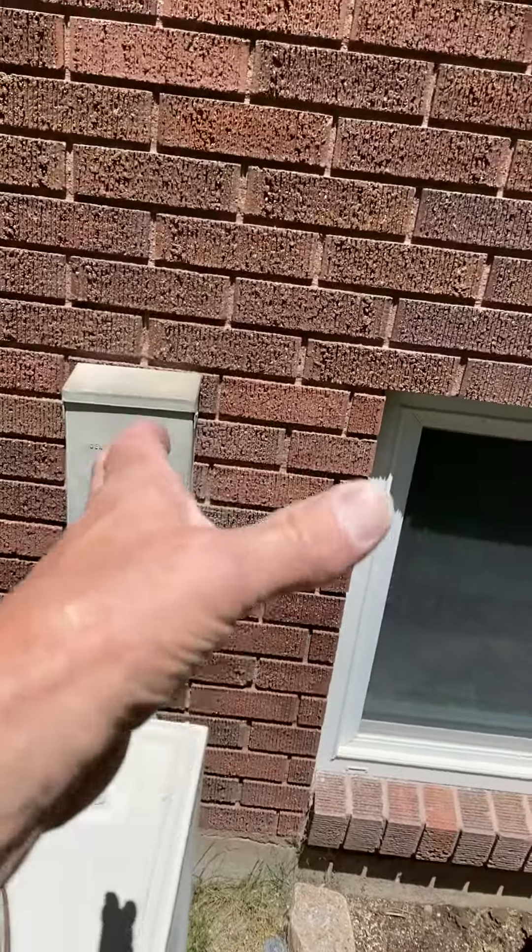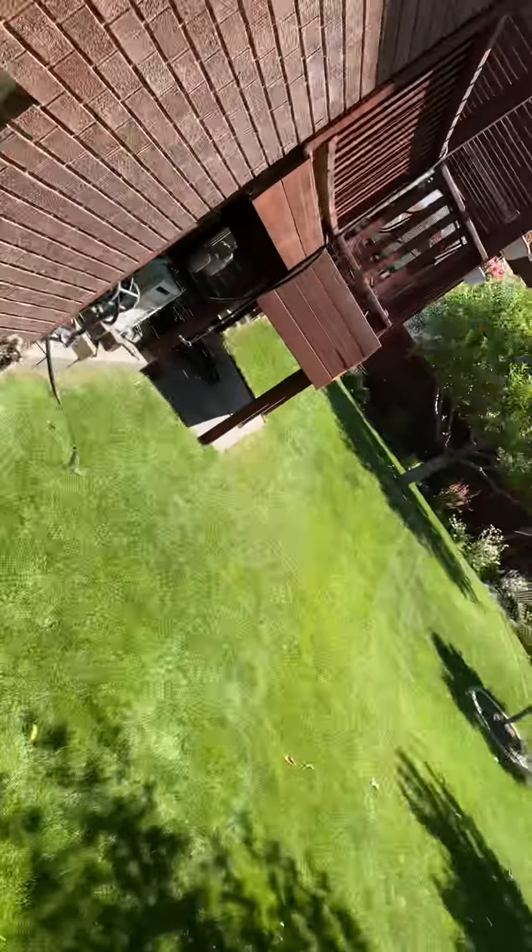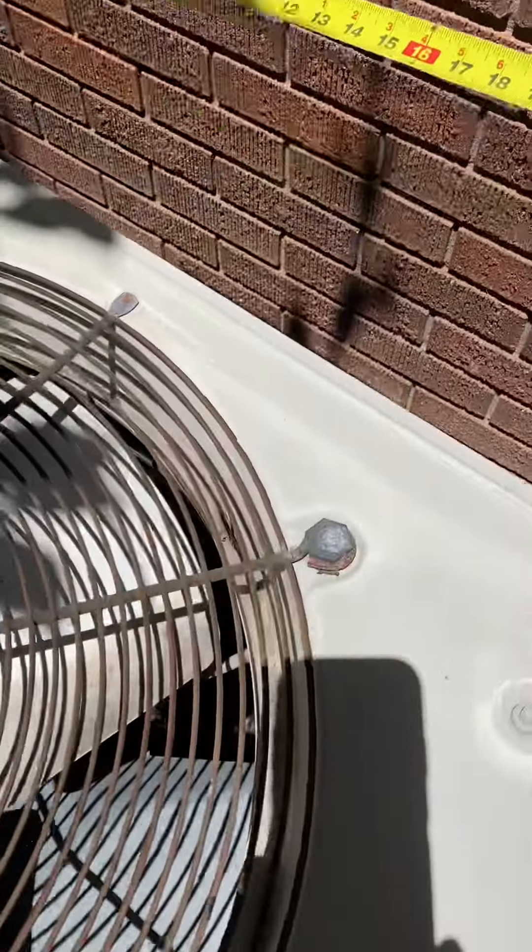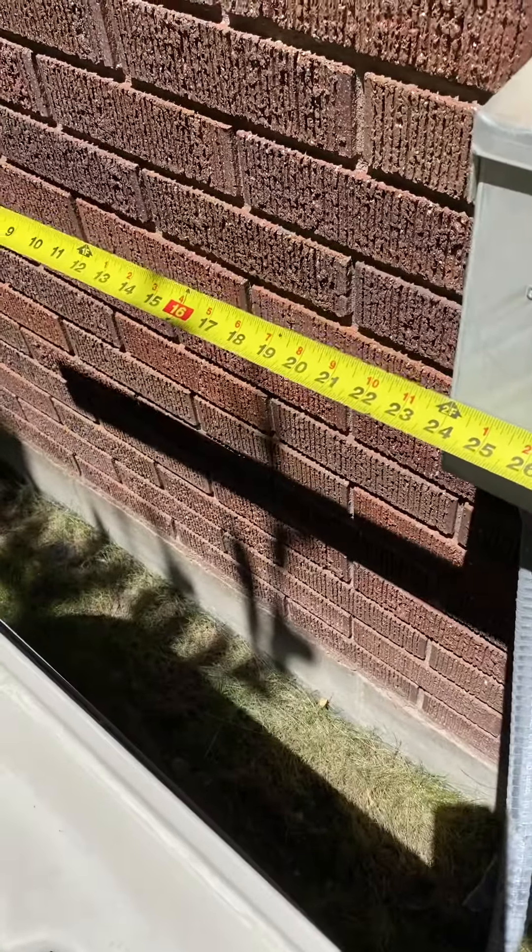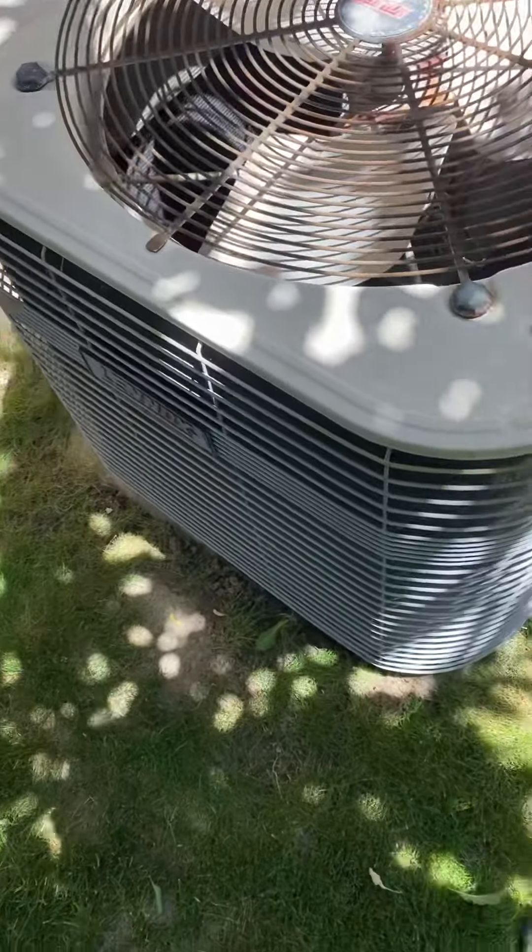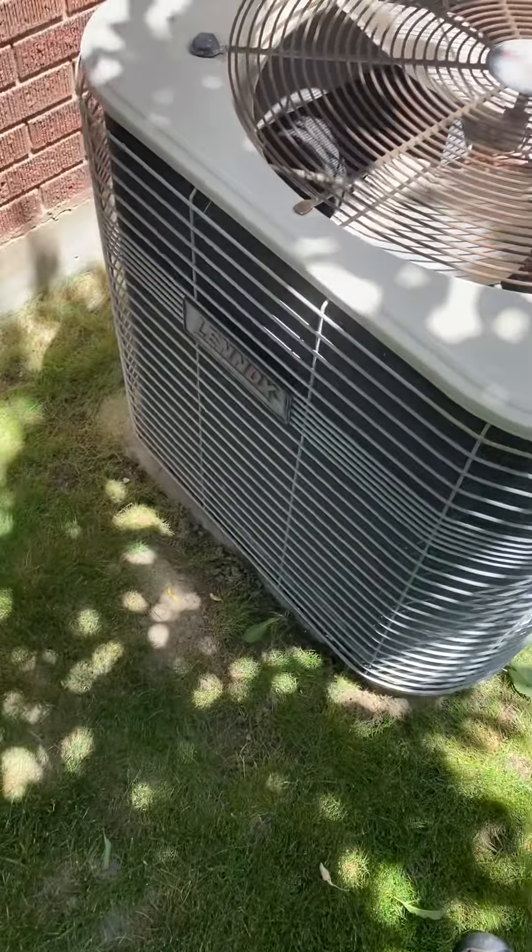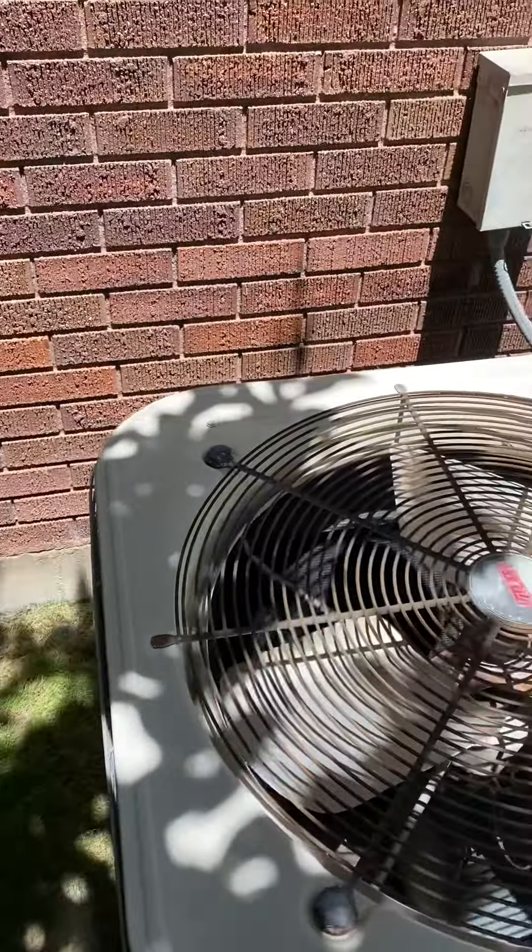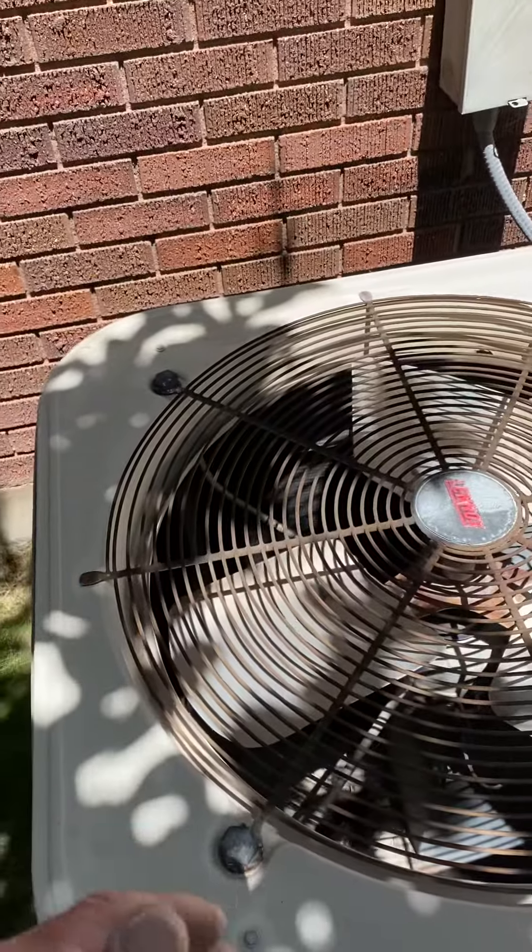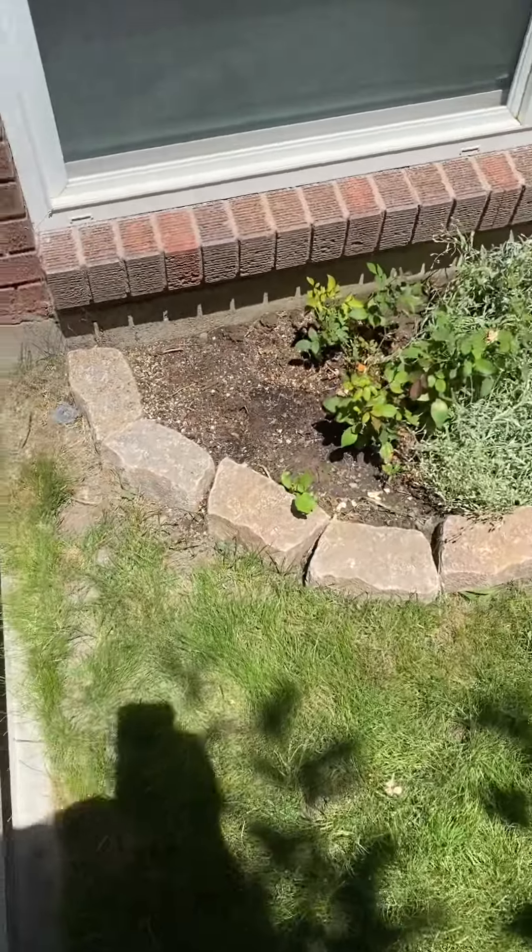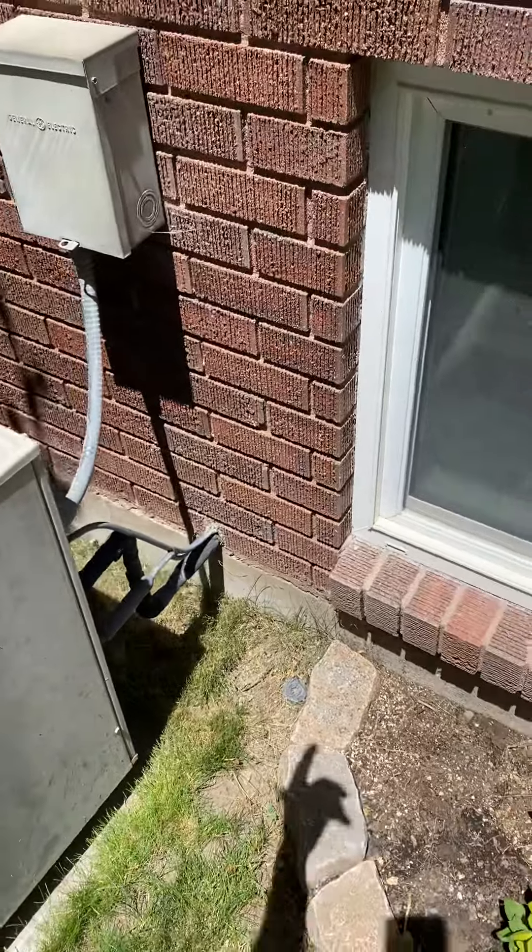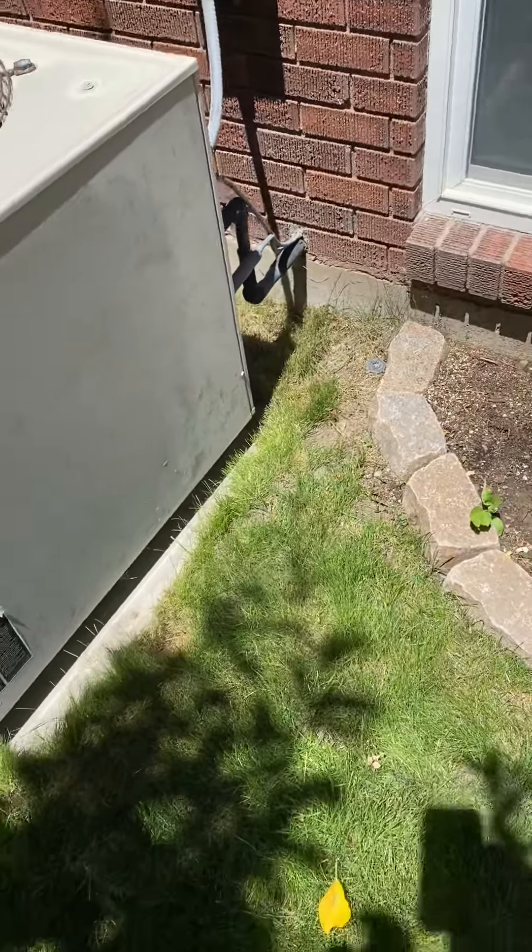So right now the AC sits in front of the disconnect. Our new unit is like 28 inches. So I'll give you a new 30 by 30 pad. Just sit it on top of this pad but scoot it over so we don't block the disconnect. Flush the lines and we use the existing disconnect. That's it.